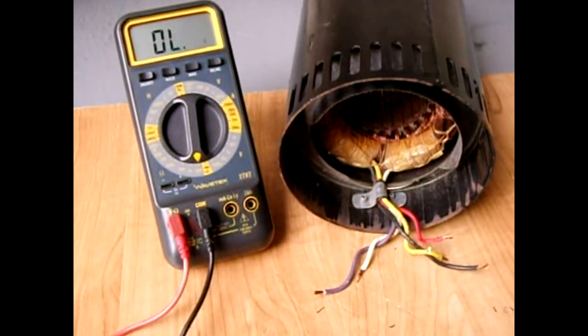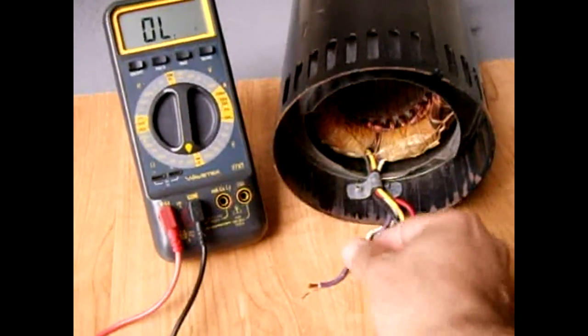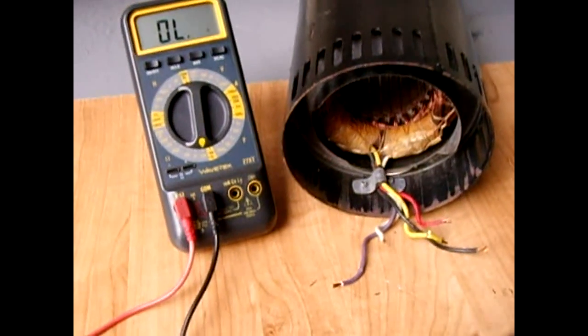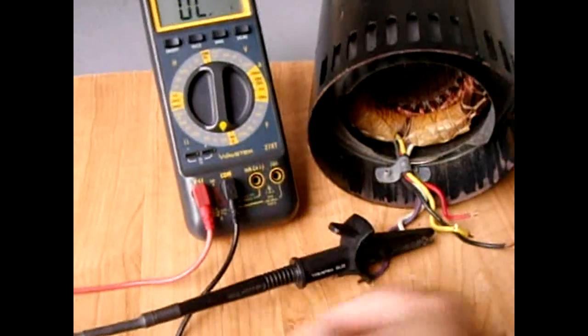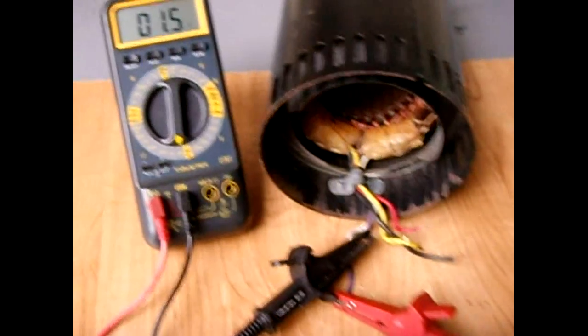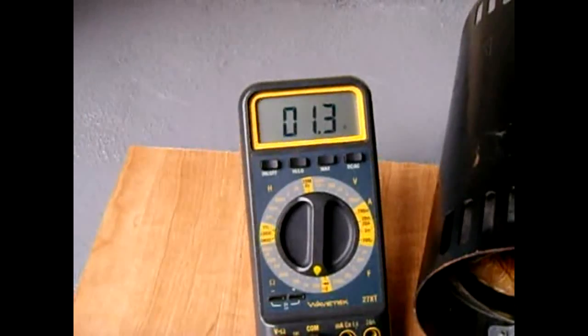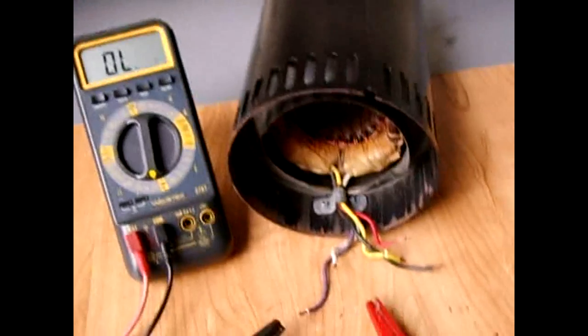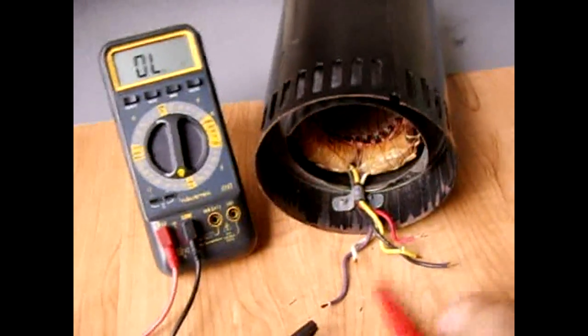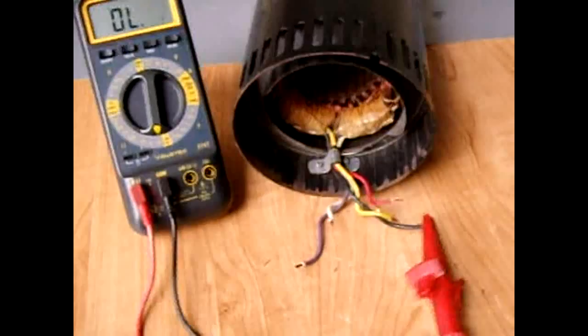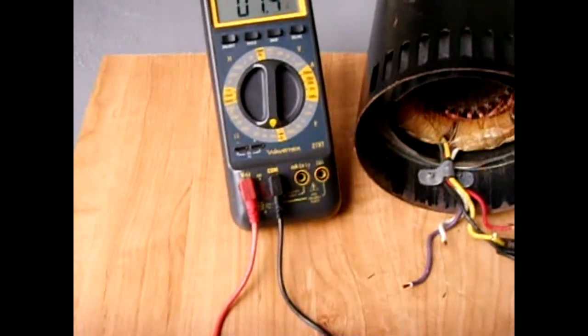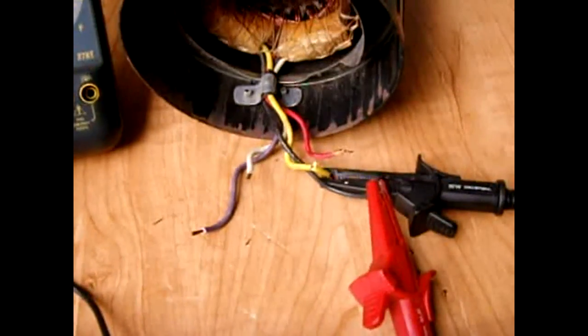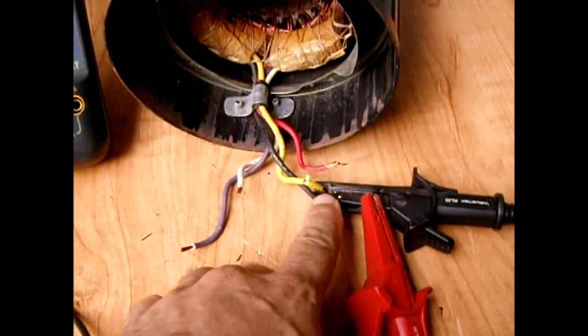All right, so we're going to test the windings. We're going to check the main winding first. This is one side of the main winding right here, white and purple. That's right around 1.2. Other side of the main winding right here, and that is also 1.2. So by doing these measurements you can see black and yellow is at 1.2 ohm, purple and white 1.2 ohm. Clearly identify the two windings.